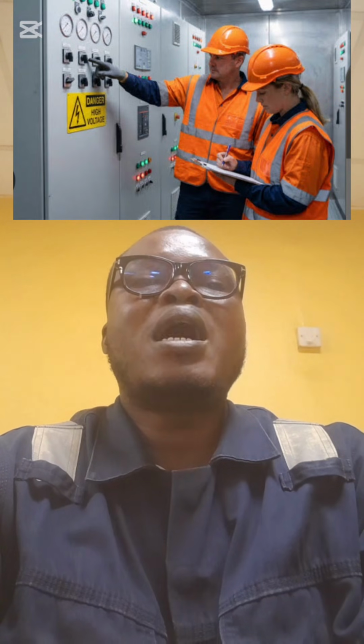Identifying means correctly identify the equipment to be worked on from approved drawings. Every site must have an approved drawing, and any new installation done on site must be modified on a drawing. Secondly, de-energize. De-energizing means switch off and disconnect from all sources of supply.